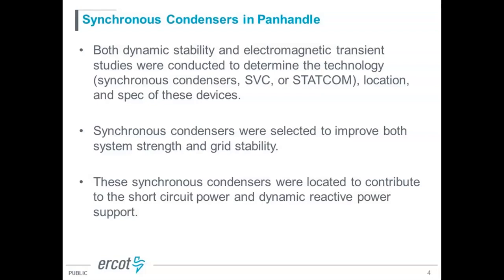As a result, condensers were selected out of these three, mainly for two purposes: to provide system strength in terms of short-circuit power, and at the same time to provide dynamic reactive support to improve grid stability. Those are really the two major driving points that determined the need for synchronous condensers in the Panhandle.